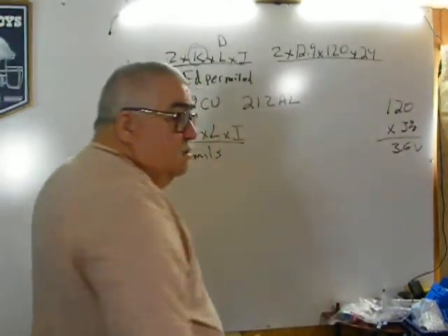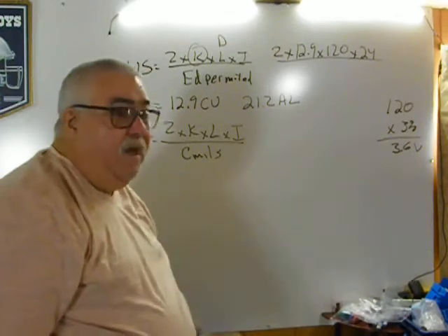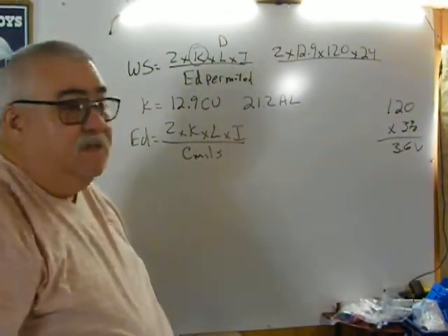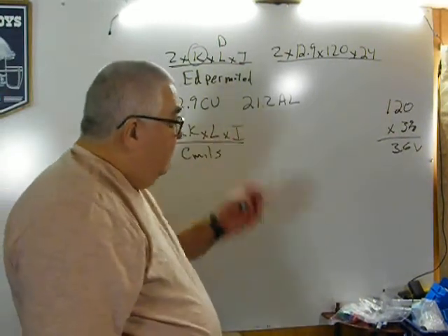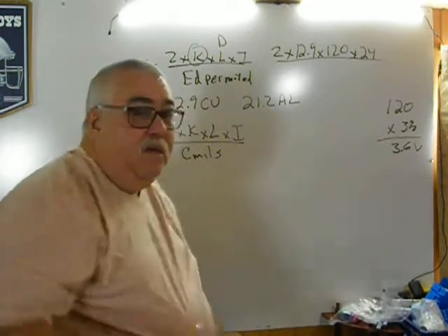The voltage may change, but that 3% doesn't change. So it may be 120, 240, 277, 480, 600, 1000, it doesn't matter. From the last breaker to the load, it is 3%.